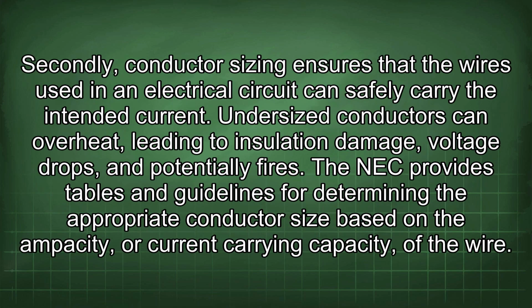Secondly, conductor sizing ensures that the wires used in an electrical circuit can safely carry the intended current. Undersized conductors can overheat, leading to insulation damage, voltage drops, and potentially fires.